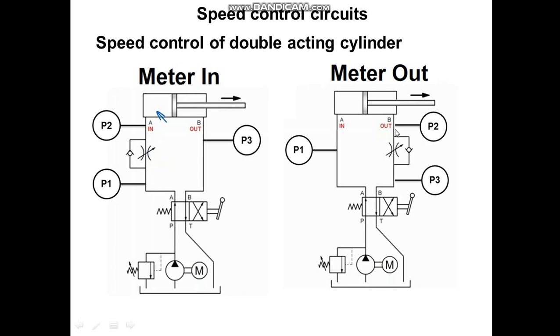And here there is no arrangement with which we can relieve that pressure, because the restriction to the flow is made over here. Since the pressure relief valve is connected here, the higher pressure generated by resistance to flow on the primary side will be relieved by the pressure relief valve. But if we partially close this particular valve, pressure will be created in this line.